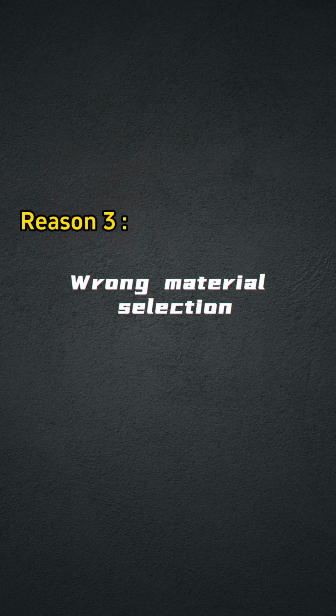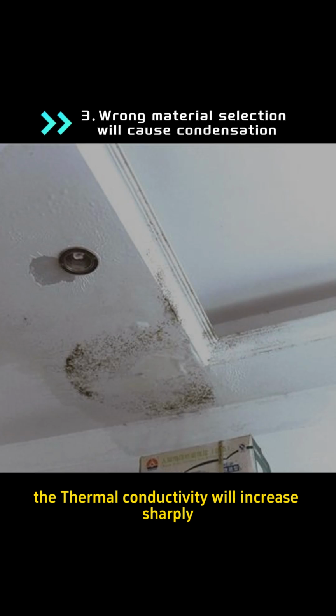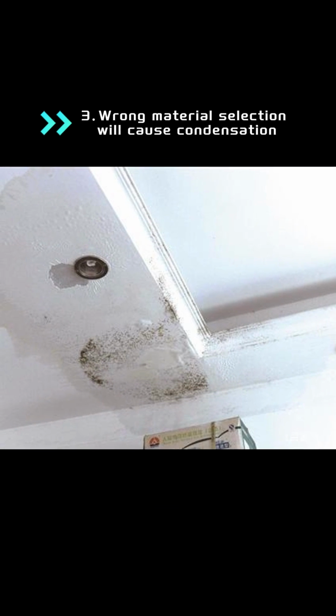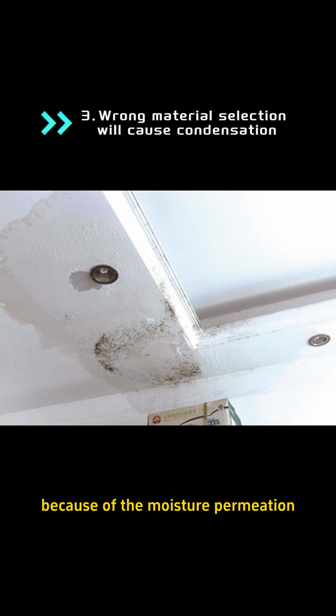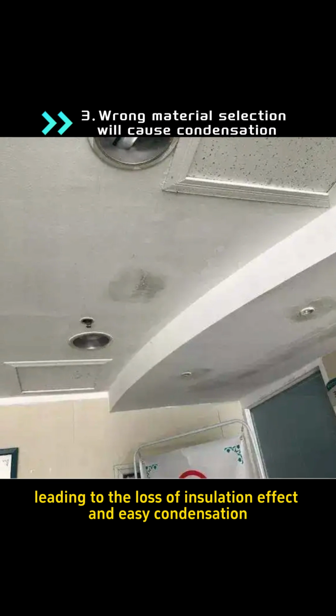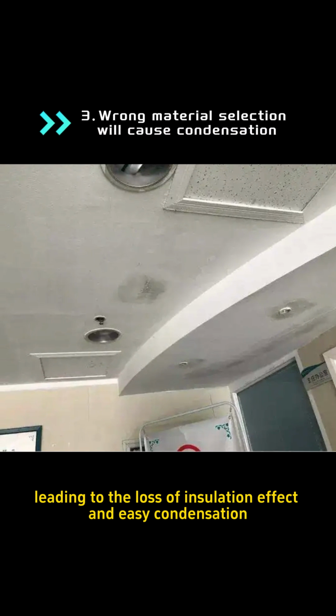Reason 3. Wrong material selection. If you choose the perforated insulated material, the thermal conductivity will increase sharply because of the moisture permeation, leading to the loss of insulation effect and easy condensation.